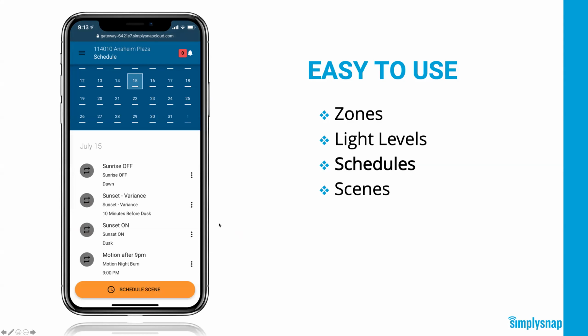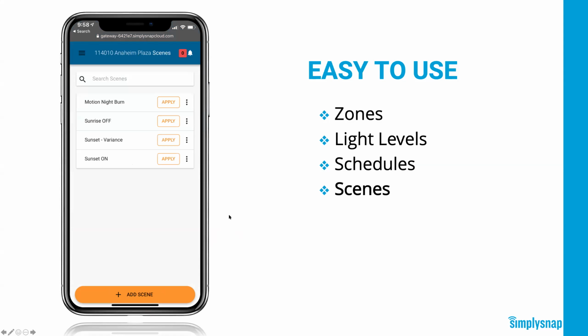That's very straightforward. Now, I mentioned that overnight occupancy schedule—let's say the user wants to change the dimming level when occupancy is detected. Right now the system is set up so that when a car drives through or a zone detects occupancy, the lights come up to 100%. They've noticed there really isn't a significant light level difference between 100% and 60% dimming.